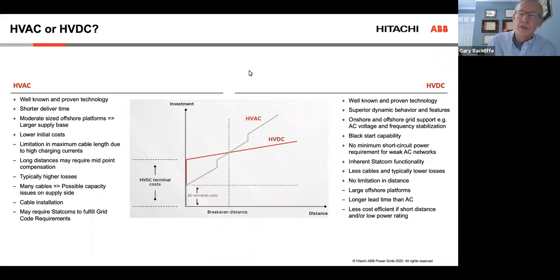The losses are really being driven in large part by the capacitance associated with the cable. So you can see that you have a higher first cost with HVDC. That's the cost of the converter stations.